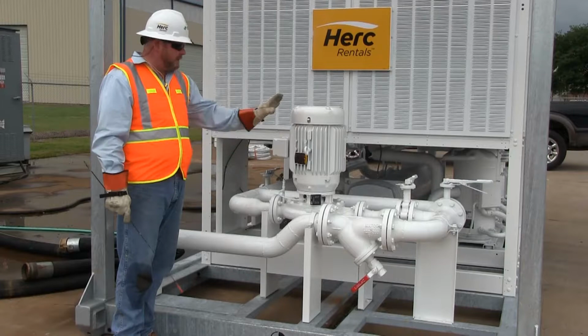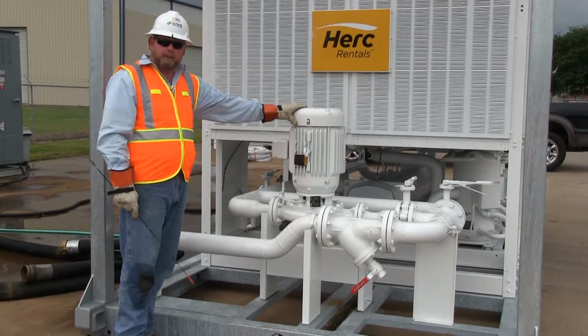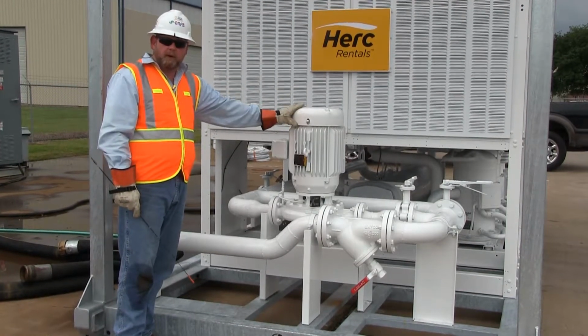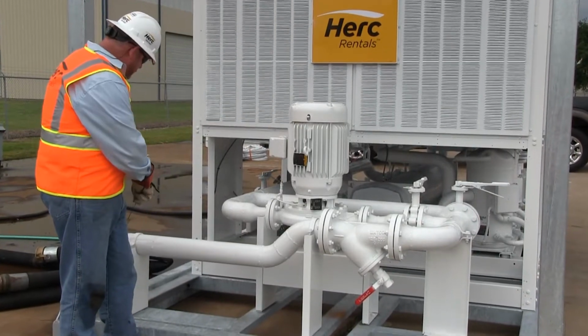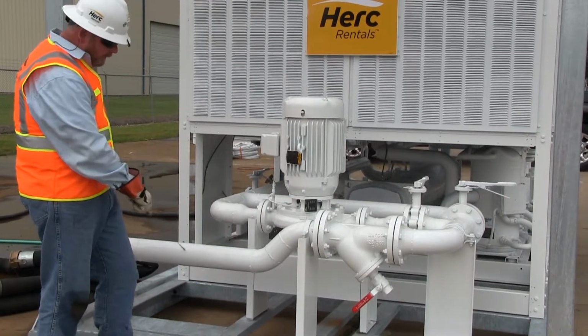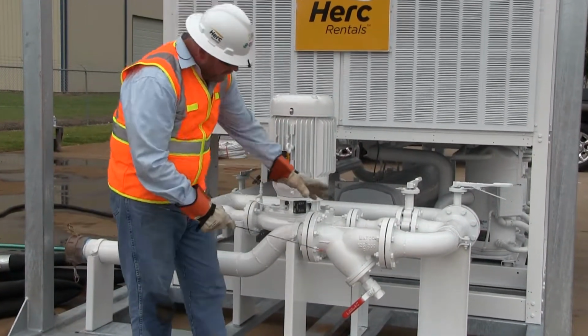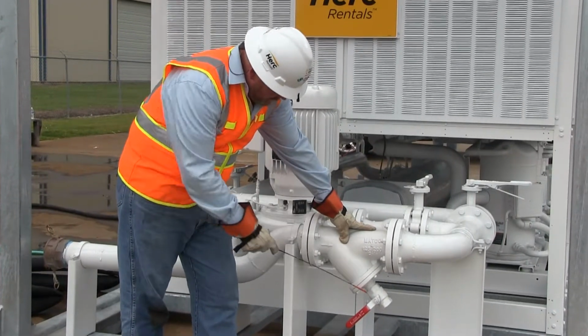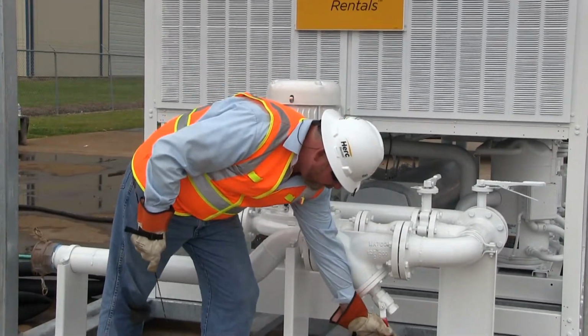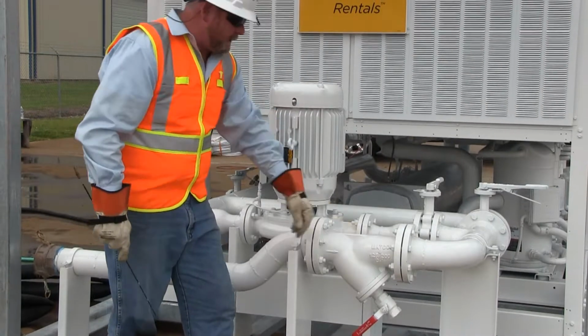All of our chillers have an integrated circulation pump on board as part of our package. The inlet connection, which is the female cam lock, is here. The water flows through the piping, and this is an inlet strainer, an inline strainer with a blowdown valve here at the bottom. That catches any debris.